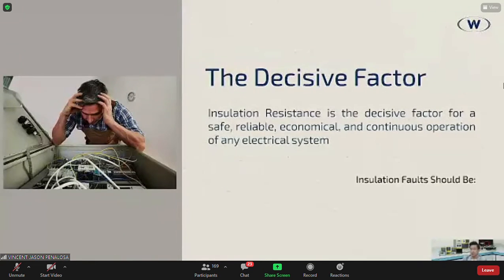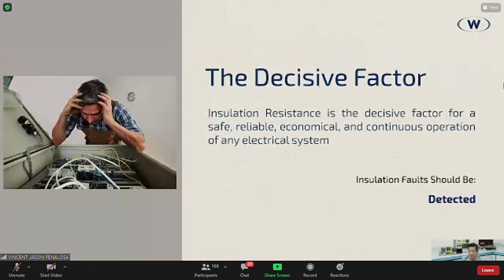So I guess all of you will agree with me that insulation resistance is the decisive factor for a safe, reliable, economical, and continuous operation of any electrical system, right? So I guess you all agree with me there. Therefore, insulation faults should, number one, be detected. Sometimes this is easier said than done, near impossible. It depends on the kind of system you have and the size of the system you have. Even worse, for some strange reason you found it, and then your boss tells you, you detected it, go out and find it. Location is also very difficult. One of the easiest things to do when it comes to insulation faults is to actually eliminate it. Why? Because something happened already, you know where to go. So remember these three things: detection, location, and elimination. Those things are very, very important whenever we're trying to monitor or look for insulation faults.